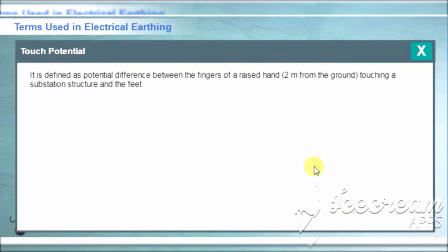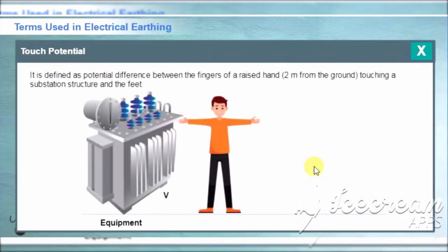Touch potential. It is defined as the potential difference between the fingers of a raised hand 2 meters from the ground touching a substation structure and the feet of the person. For instance, if the distance from ground is 2 meters, then the touch potential should be small, within 100 volts, so that the person does not get a shock even if the ground structure is carrying a fault current.